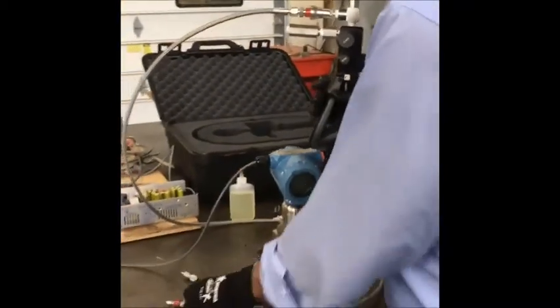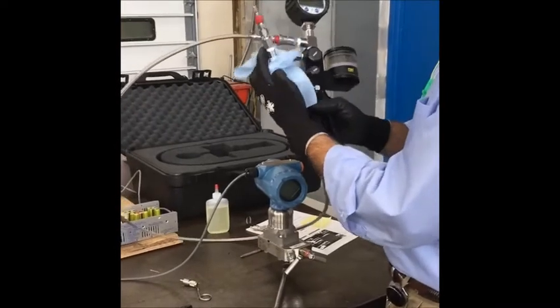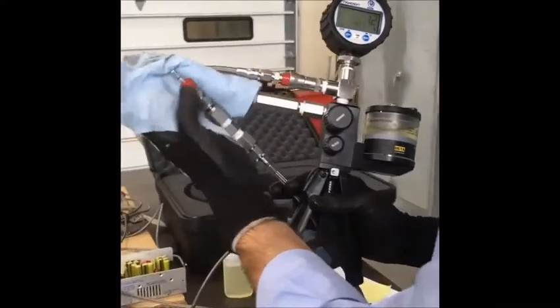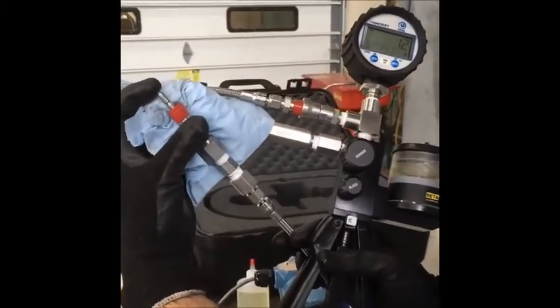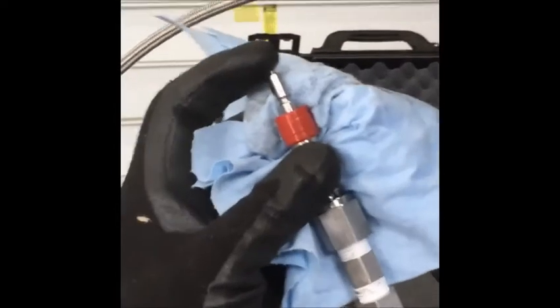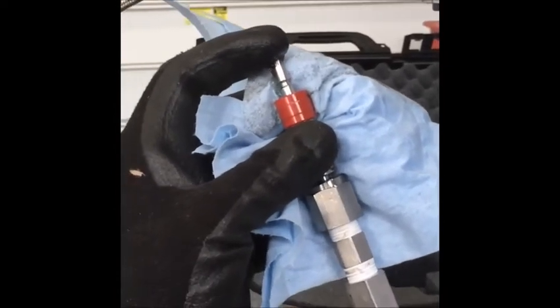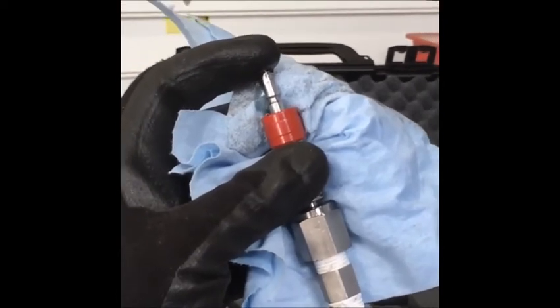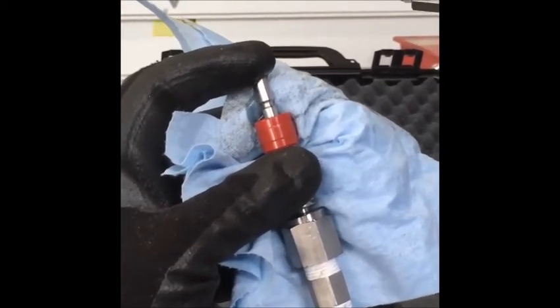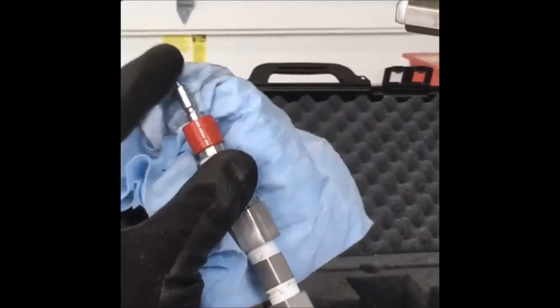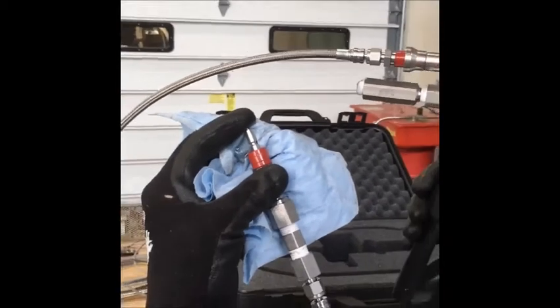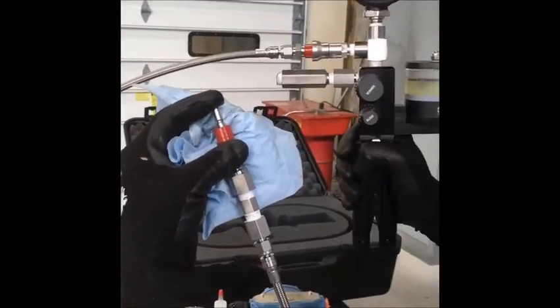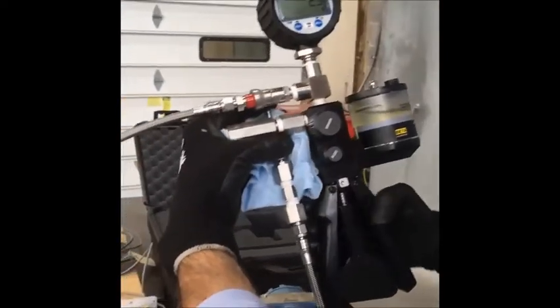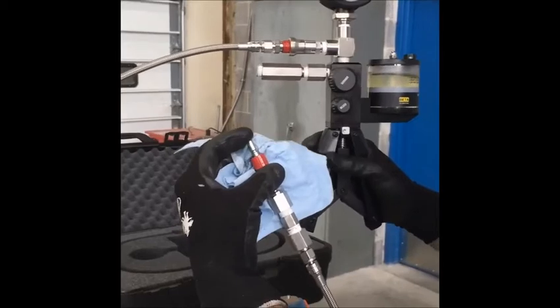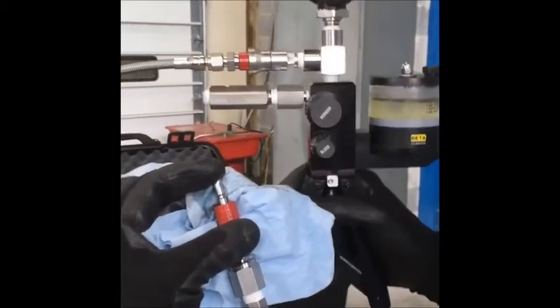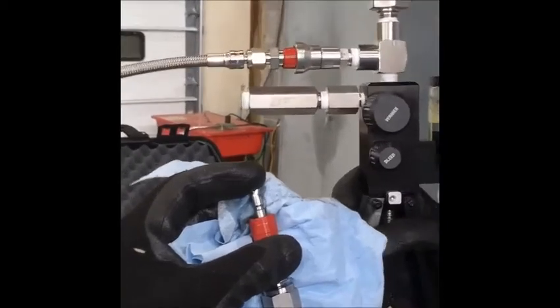I'm going to use a rag here on the end of the hose. And I'll let him zoom in here. There's a little check valve right on the end of the hose that if you push that in with your finger, as you pump with the pump, you should begin to see oil coming out of the end of the hose. Now this is important because you don't want to trap air in the hydraulic hose. It makes the possibility of pushing air into the refrigeration system, which we don't want. We'd rather have just oil during the calibration. So we will pump with this little button release until we see some oil coming out there at the end of the hose with no more bubbles, really.